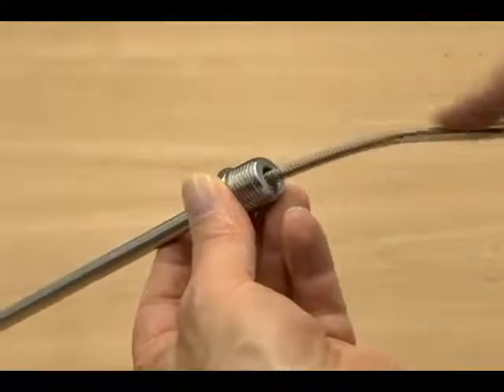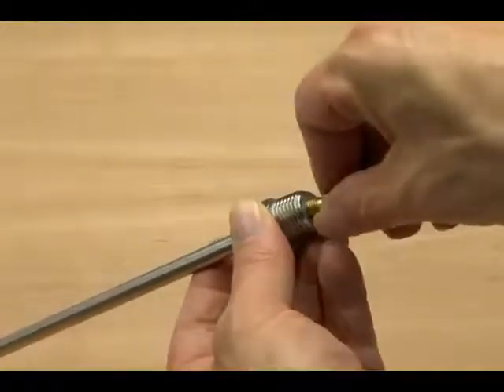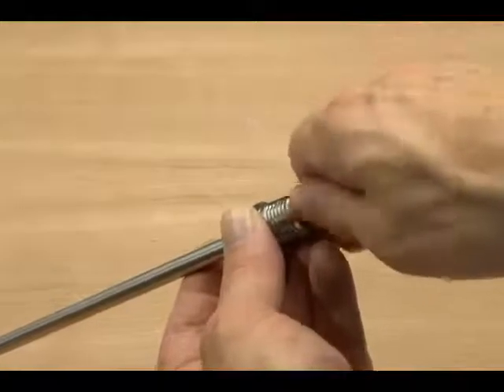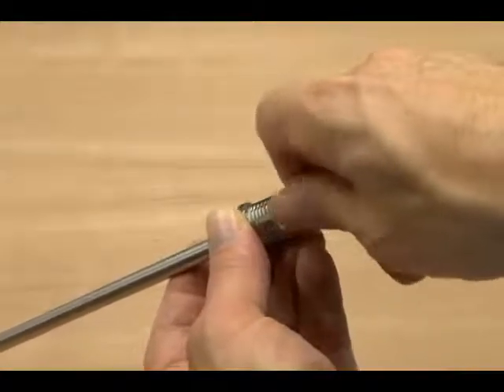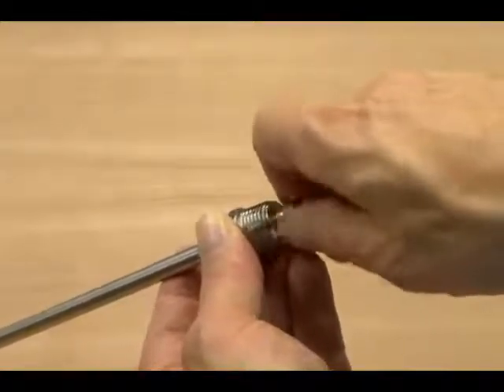If you're using a screw-in retainer bushing, compress the spring and screw the bushing in place. This will keep the probe tip in direct contact with the thermal well bottom. If it's too hard to compress the spring, simply cut a little more off.